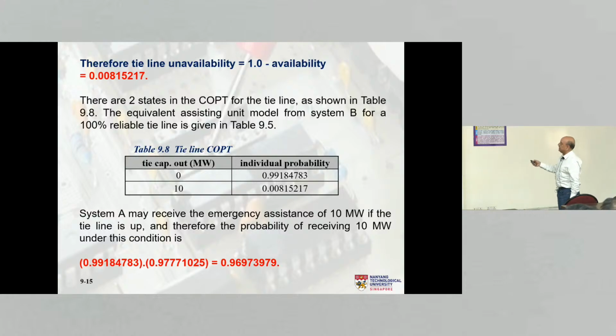Okay, so the tie line unavailability is 1 minus availability, which is this particular number. I think we all can calculate that. So now there are 2 states in the COPT for the tie line, which is the same as before, because it is still a 10 megawatt tie line. So I can only transfer 10 megawatt. Remember, we got the 2-state model before, using this availability. The equivalent assisting unit model for a 100% reliable tie line.